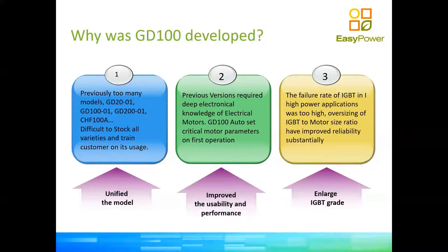In the previous versions, a lot of the performance was underrated. The older models required knowing certain things about your motor — resistance, inductance, and other variables — that sometimes don't even appear on the motor data plate. That led to a lot of wrong information being inputted into pump inverters and subsequent failures. Now the inverter has an automatic configuration mode: after you set the basic parameters, on the first start the pump inverter measures the electrical parameters from the pump circuit, reducing guesswork to the absolute minimum. Additionally, the inverters are now oversized — they have additional transistors and IGBTs — so they could reduce the current per IGBT, keep them cooler, and substantially reduce the failure rate.